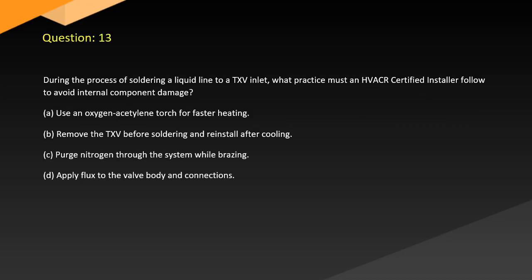Question 13. During the process of soldering a liquid line to a TXV inlet, what practice must an HVACR certified installer follow to avoid internal component damage? A. Use an oxygen acetylene torch for faster heating. B. Remove the TXV before soldering and reinstall after cooling. C. Purge nitrogen through the system while brazing. D. Apply flux to the valve body and connections.